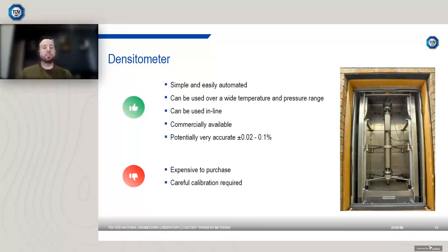Now, what are the advantages and disadvantages of this type of device? Well, they're relatively simple and easily automated. They can be used over a wide temperature and pressure range, and they can be used in line. They're quite a mature technology as well, so they are commercially available and potentially very accurate. You can achieve as good as plus or minus 0.02% uncertainty on density measurement, provided you calibrate them.